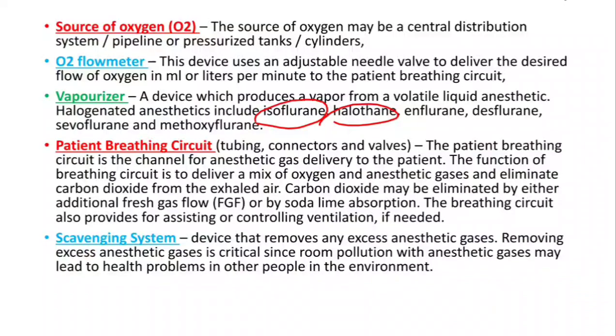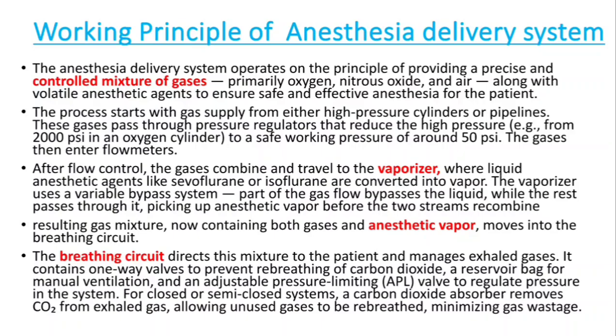Then at last we have the scavenging system. This part protects the healthcare team by capturing any excess anesthetic gases. Otherwise these gases could build up and cause long-term health effects to the staff. Now let's see how these components work all together.